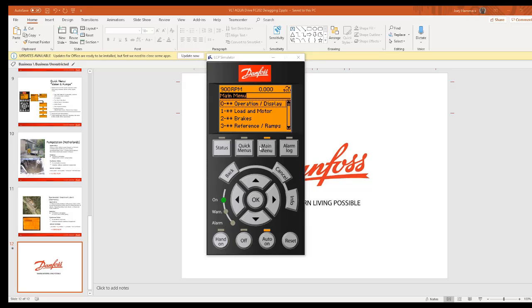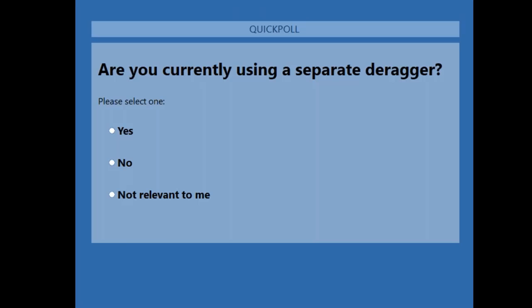Okay, this is a good time for me to send out a poll. And while you guys are answering the poll, one thing to note is that this is built into the Danfoss drive, our Aqua drive, the FC202. That is the only drive that it is built into, but it is free of charge. There is no software update required or extra piece of software. It is included with the drive. So that's a cost savings opportunity for those of you who are responsible for pump stations and lift stations and that kind of thing.